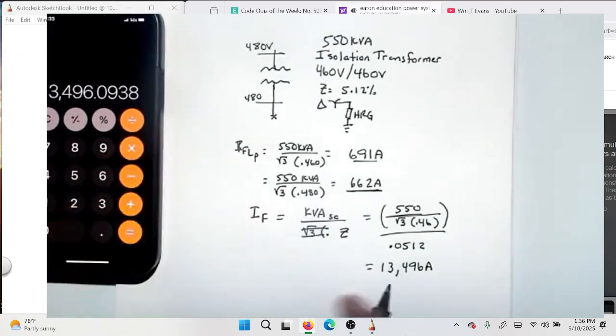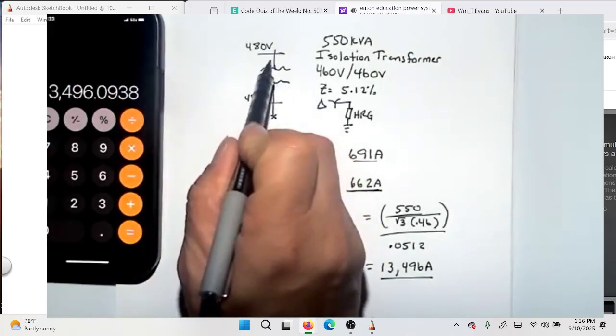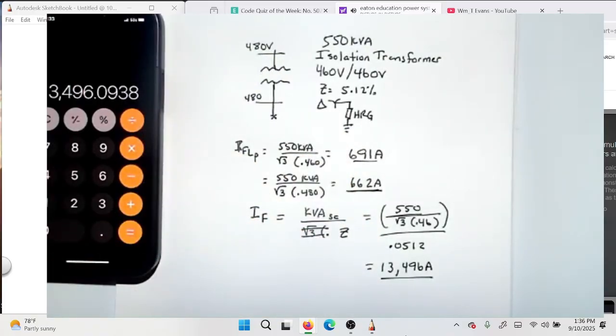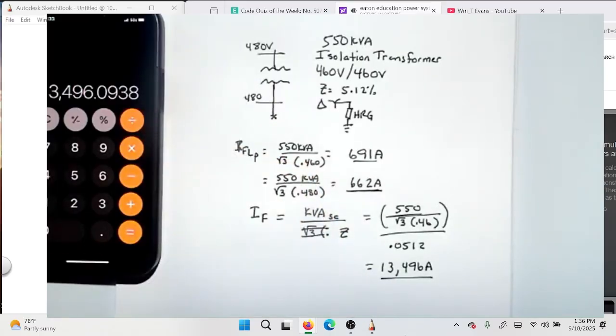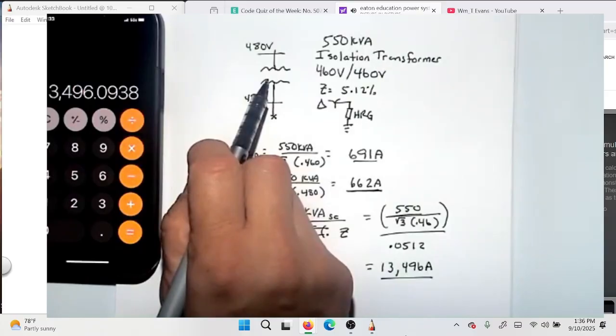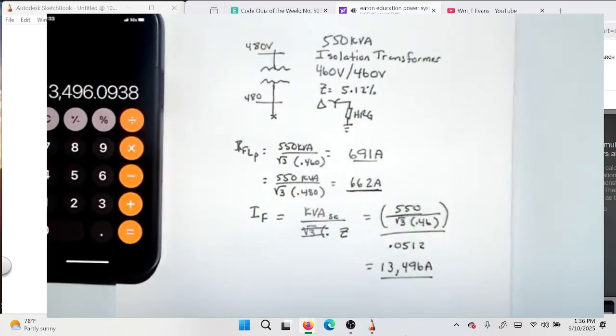If we have an estimated value of 13,496 amps, is it going to be that? No, absolutely not. It's going to be probably less than that. Why is it going to be less? Because remember, we ignored our primary impedance of our source above that. And a lot of times in this case, especially where you use an isolation transformer, the transformer upstream of this might not be very small or very big. In fact, it might be closer to the range of this transformer. So we do have to take that into account sometimes in a more formal study. But again, it's going to knock that number down.